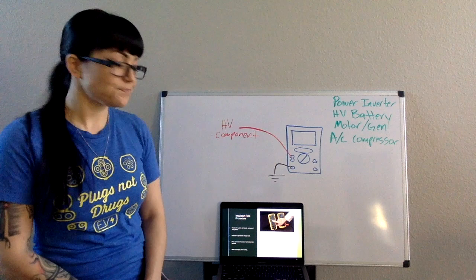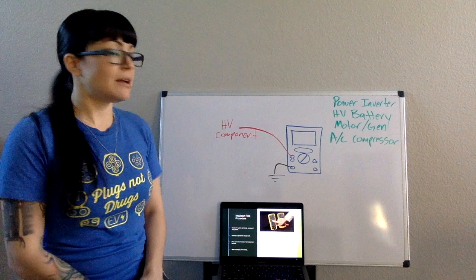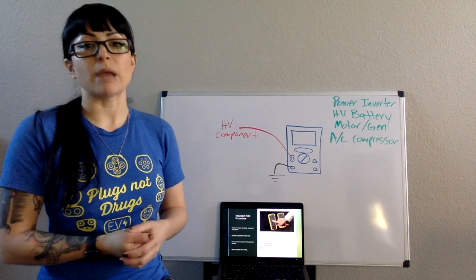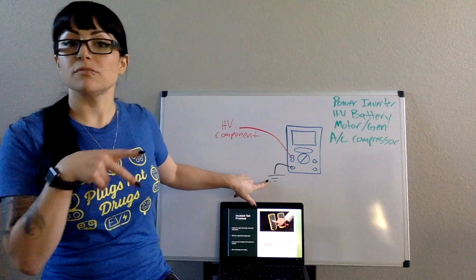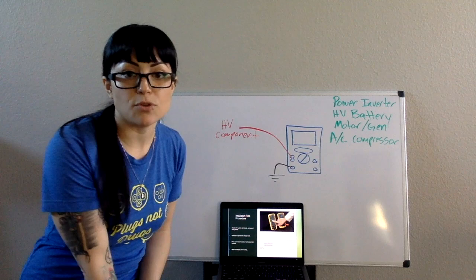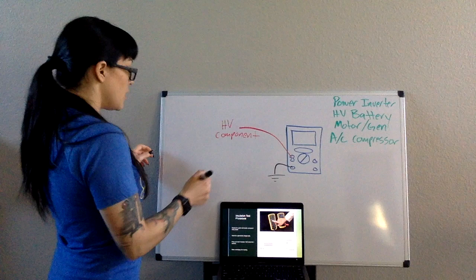Once you're ready, you're going to need to hook the voltage tester up. I like using alligator clips for this one unless you have multiple hands or multiple people testing. You can touch one lead to chassis ground or wherever you're concerned the leak might be to. If I'm testing a motor generator, nothing should be connecting to the case itself because that would be dangerous. So I'll hook my alligator clip up for my ground on the case itself. My red lead is going to go to whatever high voltage component I think is leaking to ground or to chassis ground or to the case.